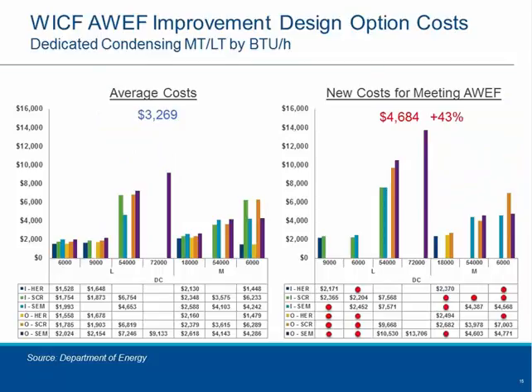I do want to point out that this is DOE data illustrated for walk-in coolers and freezers. And a word of caution: I do not believe that this is an accurate representation of the actual market itself, but I do want to point out this is how the Department of Energy is expecting to see costs to improve and costs to increase in order to improve these systems. You can see that the first one, which is the baseline cost, is about $3,269. And as I mentioned, here is your low temp, here is your medium temp dedicated condensing, and here are the capacities: 6,000 BTU, 9,000 BTU, 54,000, 72,000 BTU. And down here are the actual compression technologies, hermetic, scroll, semi-hermetic, and an aggregate of $3,269.